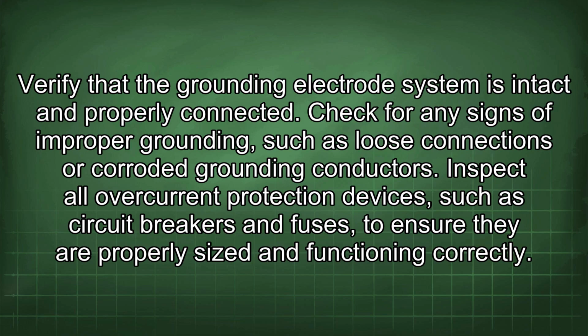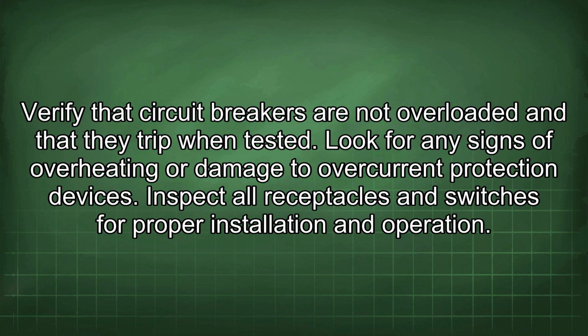Inspect all overcurrent protection devices, such as circuit breakers and fuses, to ensure they are properly sized and functioning correctly. Verify that circuit breakers are not overloaded and that they trip when tested. Look for any signs of overheating or damage to overcurrent protection devices.